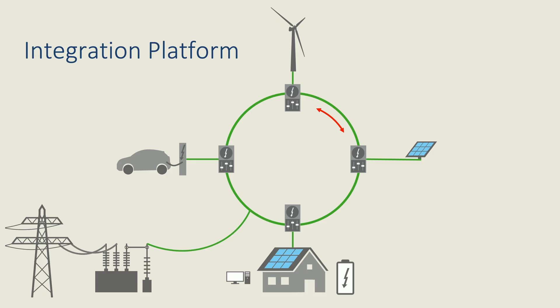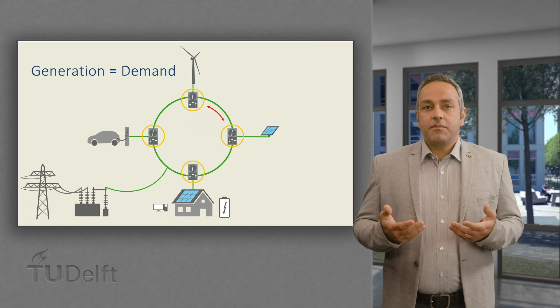If we analyze this definition, we can identify three main characteristics. First, the microgrid can be considered an integrated platform for distributed generators, storage devices, and controllable loads at distribution level. Second, control and coordination at the distribution level means that there is an active operation of the distribution grid. In contrast to a passive distribution grid penetrated by distributed sources, but where no control or coordination is implemented, a microgrid allows to manage and coordinate the available sources and the controllable loads. This allows the power balance between generation and consumption.